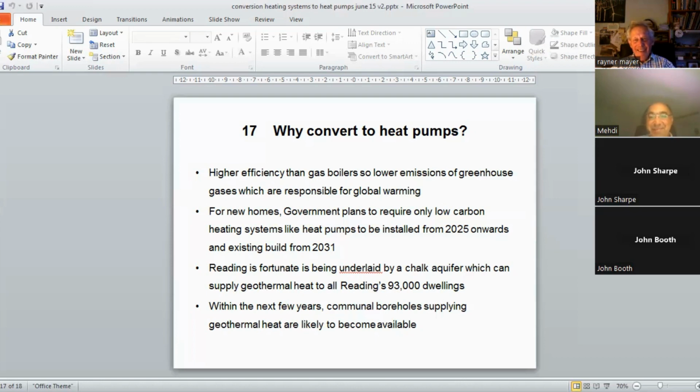I would just add something else, Caroline. Some 30 years ago, I worked with Scottish and Southern Energy in the north of Scotland to introduce ground source heat pumps in place of electric storage heaters. We got permission from Ofgem not only to install them in 100 houses, but to offer a heat pump tariff, which was substantially less than current electricity charges, one third less. The quid pro quo was that we used the heat capacity of these houses. So during times of peak demand, up to 4 hours a day, but never 4 hours at one time, the supply company, the DNO, could switch the supply to the heat pumps off. In this way, they could balance the demands.